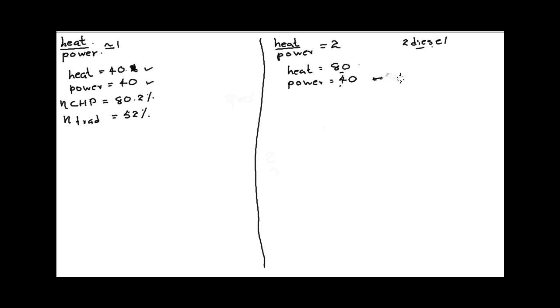Therefore, what we can do is use the same CHP plant or the same diesel engine, which will give us 40 heat units and 40 power units. We then have to find another 40 heat units somehow. In the traditional way, we used a boiler to get heat, so we can use a boiler here to get the additional 40 units. This is how we would operate when the heat-to-power ratio is increased up to 2.